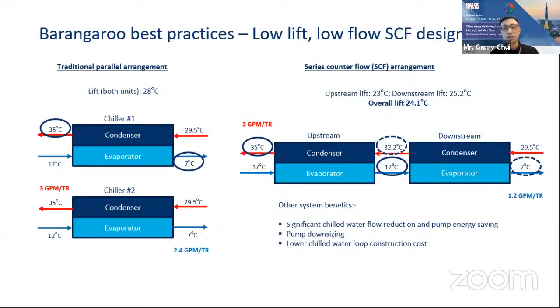On the downstream, the second chiller, it is the same case. If you look at the temperature set that the downstream chiller is operating at, the lift of this downstream chiller will be 32.2 minus 7, which is 25.2.